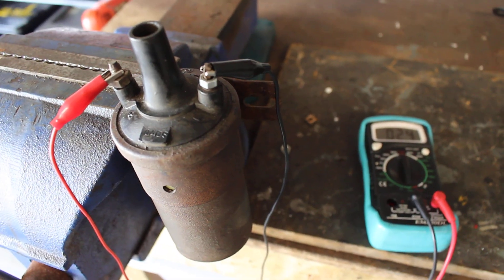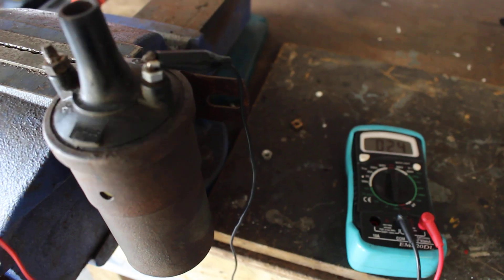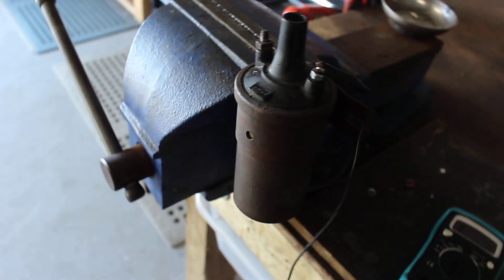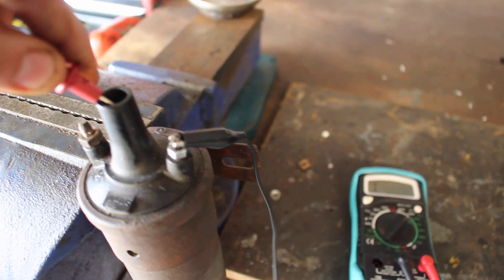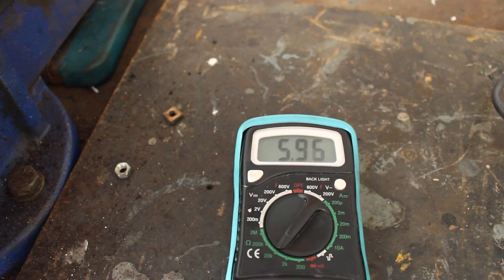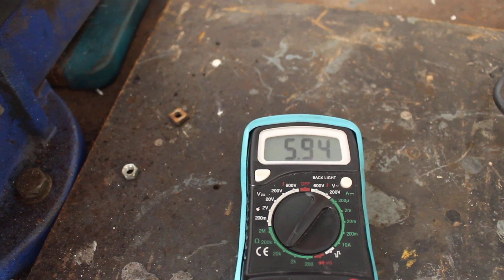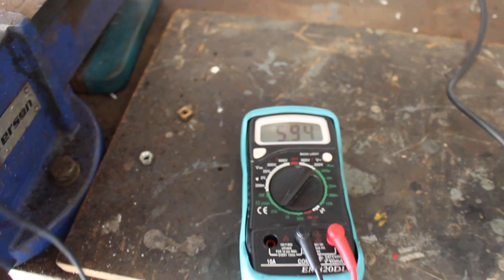So I'm going to check the secondary coil for resistance now. We turn that up to 20k ohms and put in the probe. And that's coming in at 5.94. So that seems to be functional.